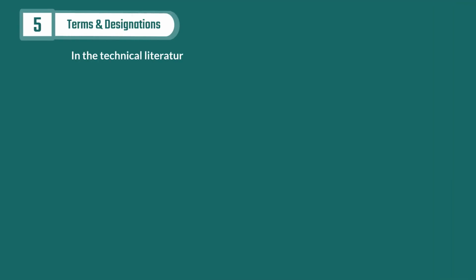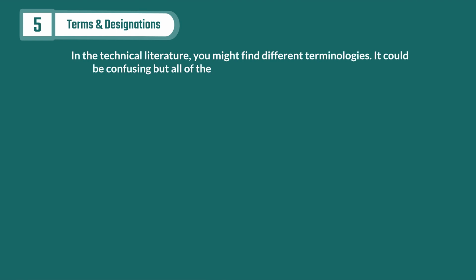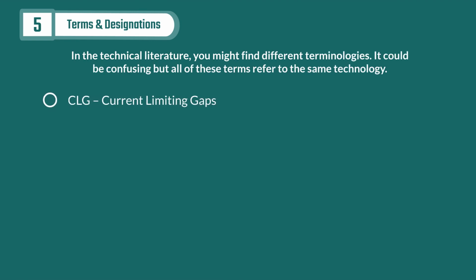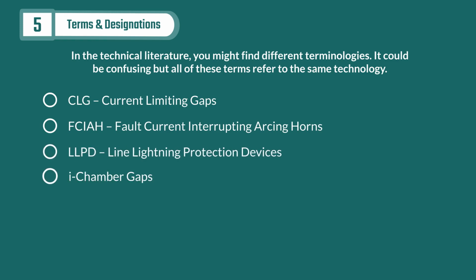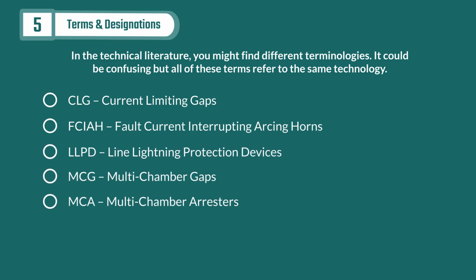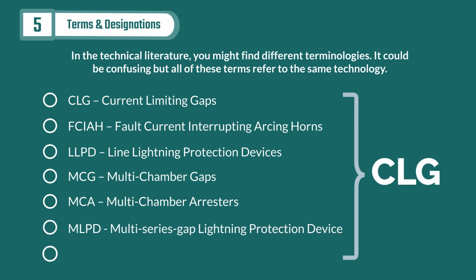Terms and designations. In the technical literature, you might find different terminologies. It could be confusing, but all of these terms refer to the same technology. Line lightning protection devices, LLPD, or fault current interrupting arcing horns, FCIAH, are common, but you can see that more terms can be found.